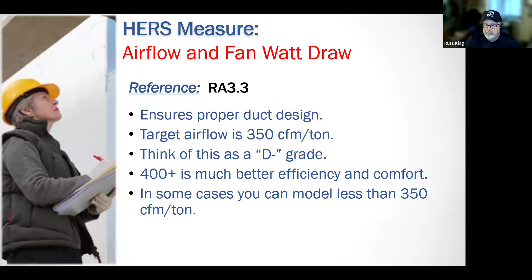Yeah, this is just a minimum. The actual CFM of what is going to happen when they turn the system on is hopefully a result of a good duct design, and that they've designed it to 400 or better. All right. But when the HERS rater goes out to test it, it has to be at least 350 per ton or it doesn't pass. The actual is going to be based on whatever it was designed to. But the code just says if you have a 3-ton system, it better be moving at least 350 CFM per ton. Okay. I hope that answered your question, Zach.